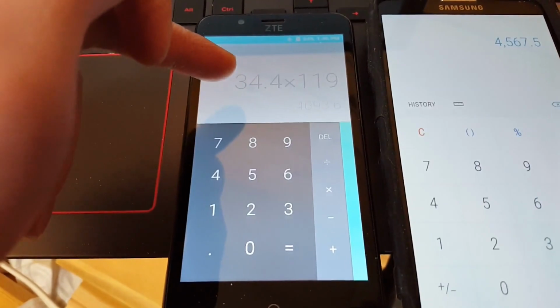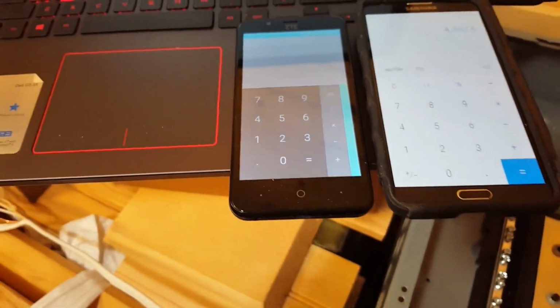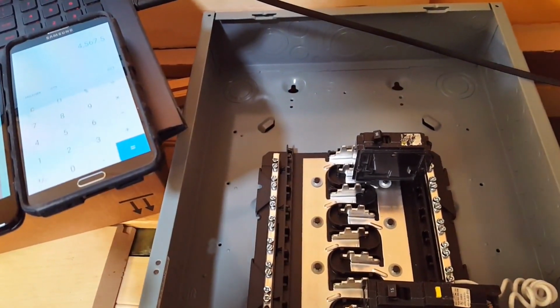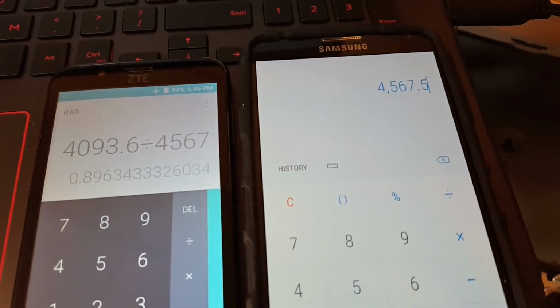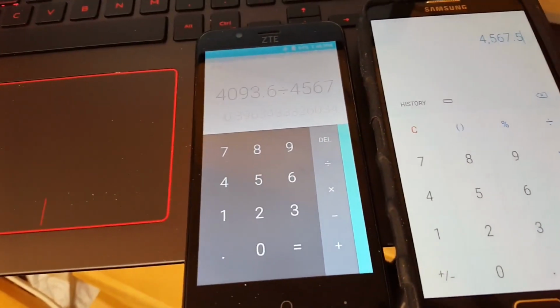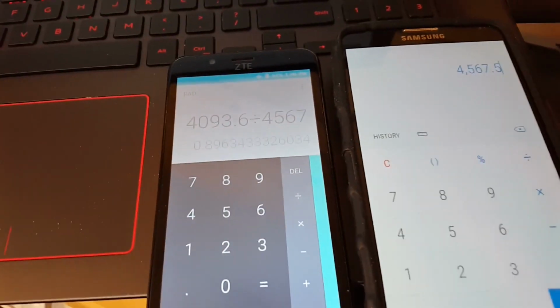Space heater loads on the AC side is 119 volts, 34.4 amps, 4093 watts. So we can now calculate the inverter losses by doing 4093 divided by 4567. That puts us right at 0.89. So that's close to 89% efficiency for the LV6548.